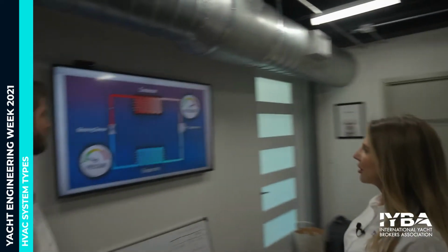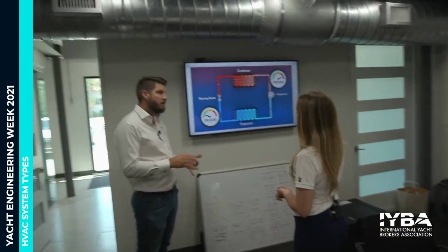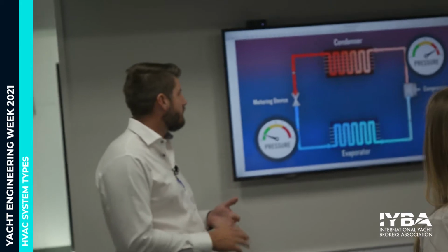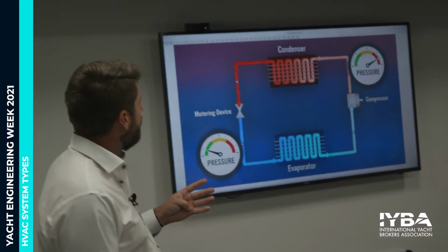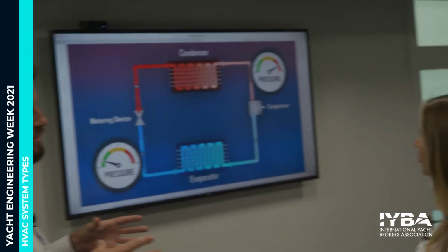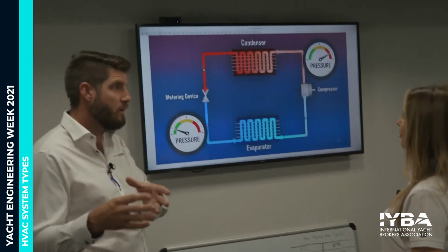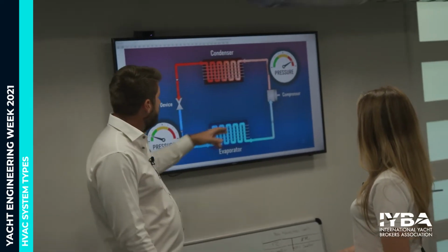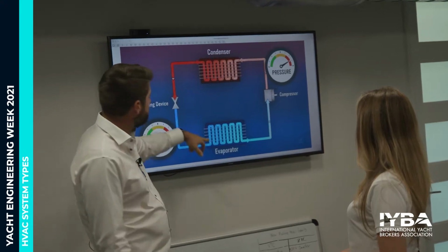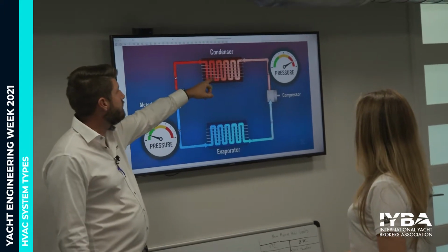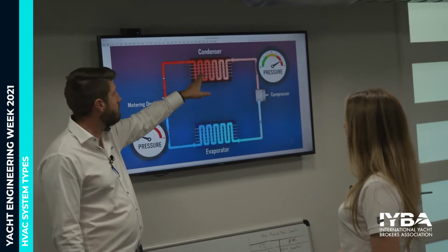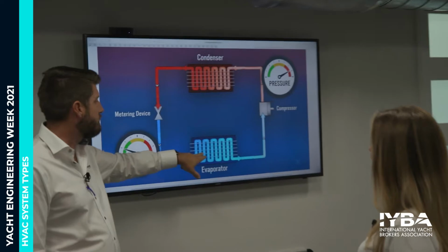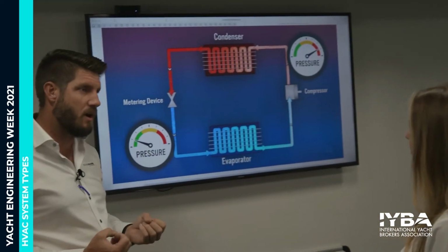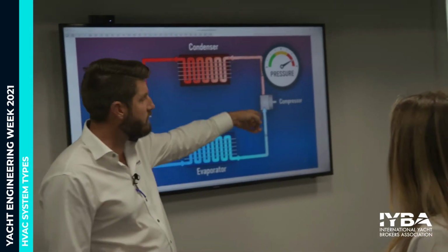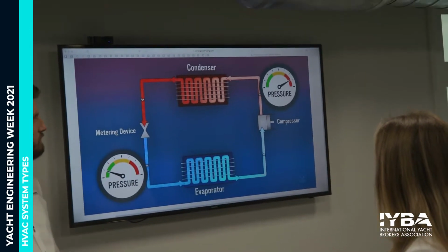So I've queued up just a quick diagram. Every air conditioning system in the world, whether it's on a yacht, a house, or a building, they all have four major components. What we're trying to do basically is move heat from one space to somewhere else that we don't want it. So every system is going to have a compressor, a condenser, a metering device, and an evaporator. In yachting, we use seawater typically to cool the condenser, and the evaporator absorbs heat out of the yacht into the refrigerant, then it goes back to the compressor, and it just keeps going and going and going. Okay, simple, right?